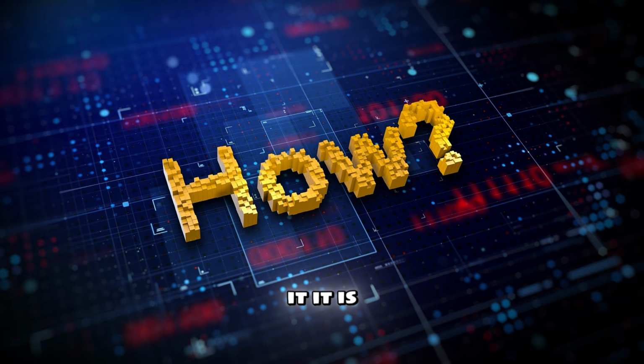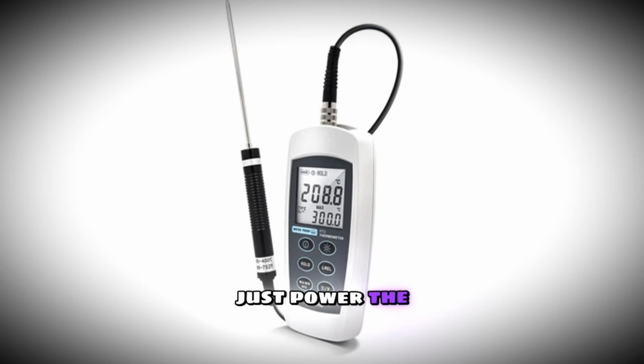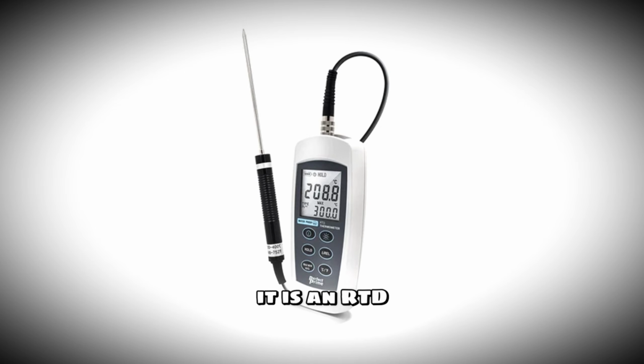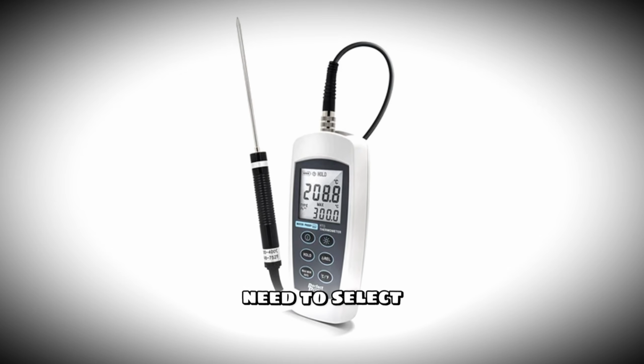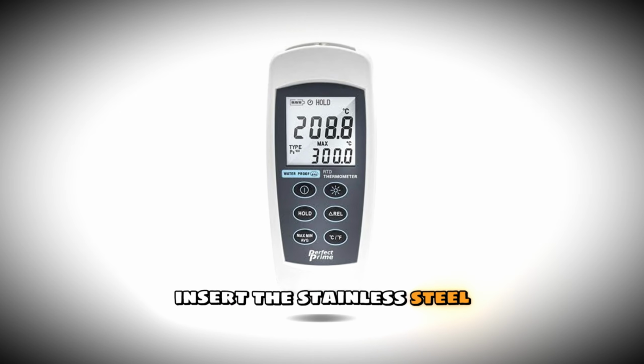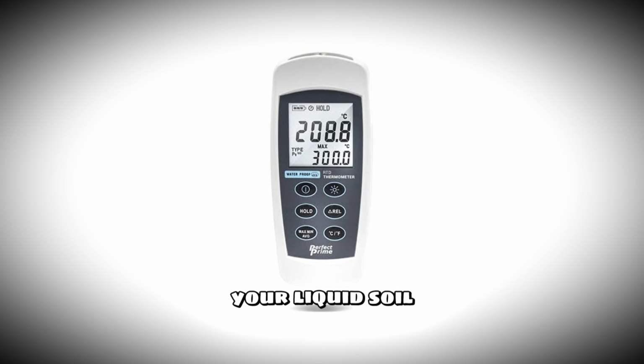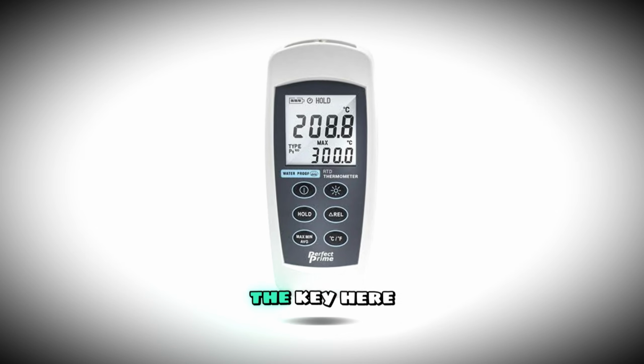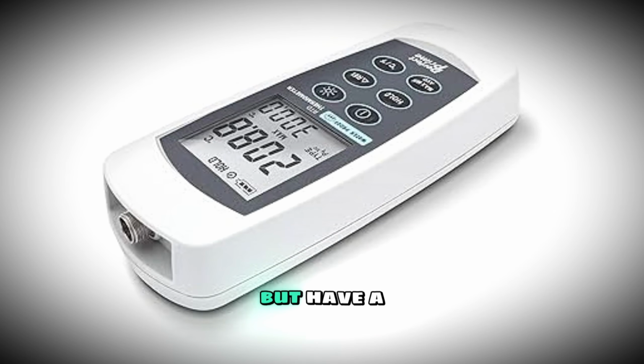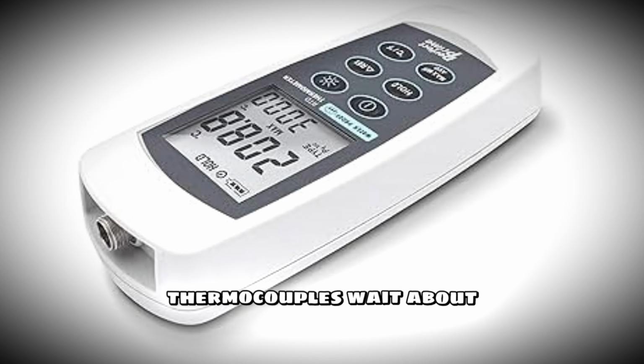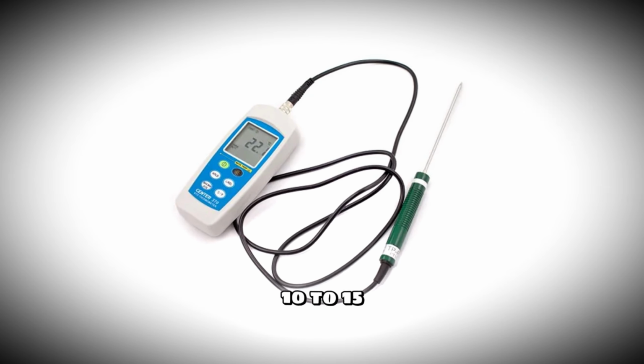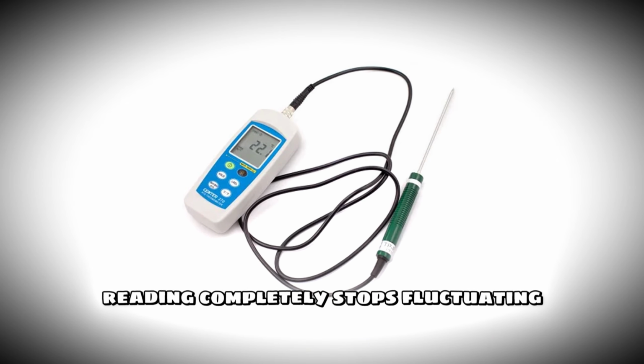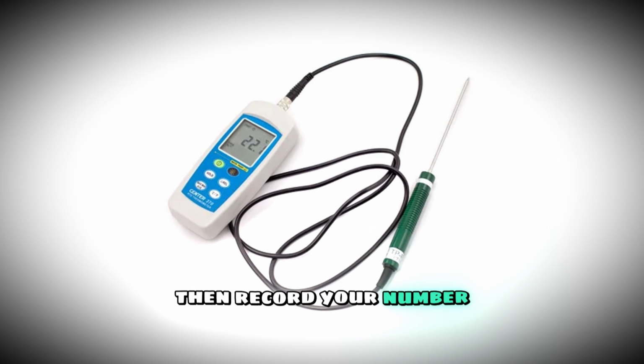How to use it? It is incredibly simple. Just power the unit on. Because it is an RTD, you do not need to select a probe type. Insert the stainless steel probe directly into your liquid, soil, or material sample. The key here is patience. Platinum RTDs are highly accurate, but have a slightly slower response time than thermocouples. Wait about 10 to 15 seconds until the digital reading completely stops fluctuating, then record your number.